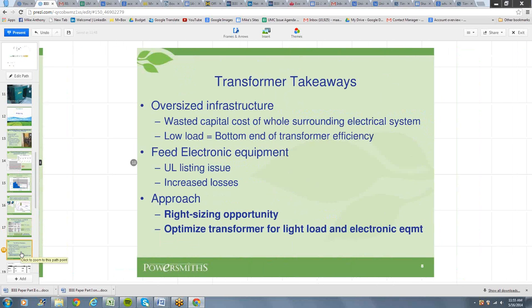So to summarize the transformer story, we've got a much bigger electrical infrastructure than we need. So we're wasting capital by putting in not just the transformer, but the surrounding breakers, conduits, conductor sizes. We're at the bottom end of transformer efficiency because we put in such a large infrastructure. The reality is, of course, we're feeding electronic equipment, so that has an impact on the load profile and the efficiency of the transformer. And what it means is you've got to be careful not to put in a general purpose transformer, because you end up with a UL issue as a function of not having a transformer appropriately listed for the load profile. So what you've got to do, obviously, is right size wherever possible, very, very important.